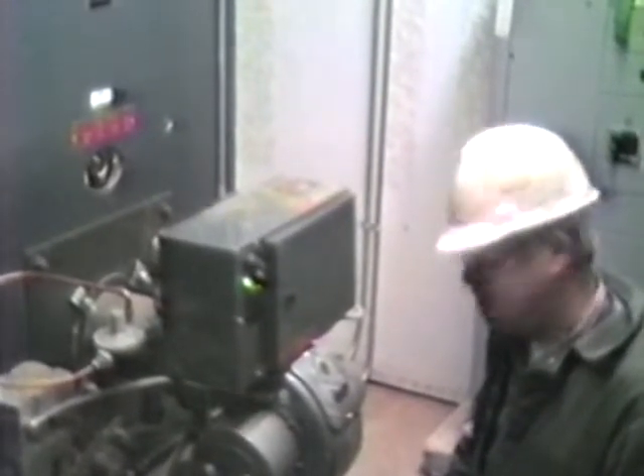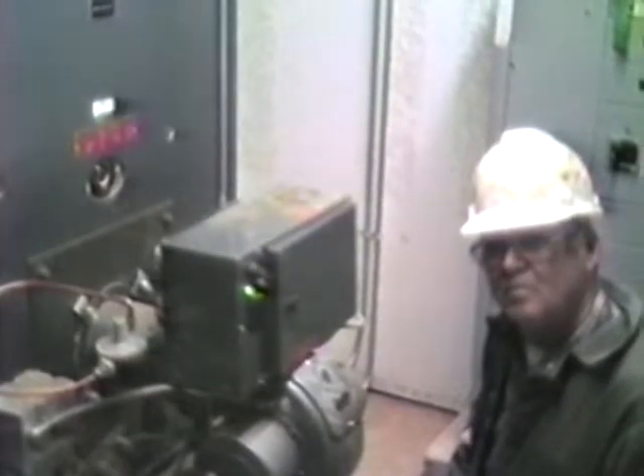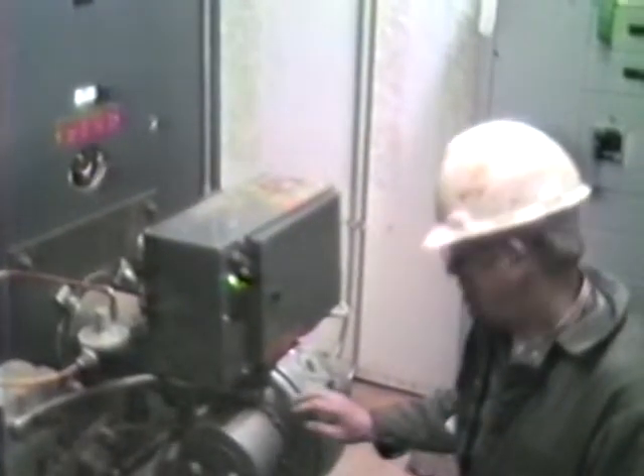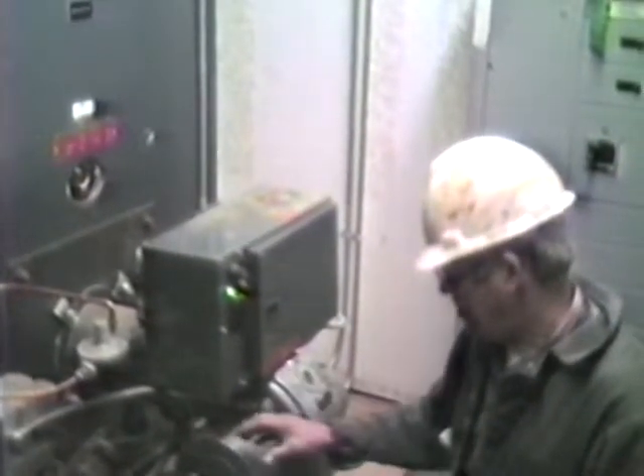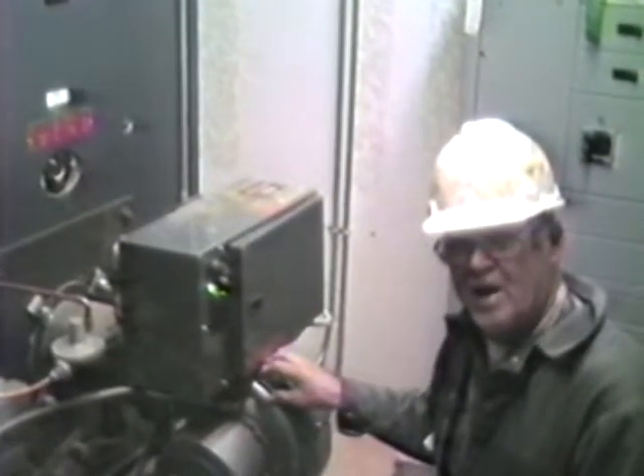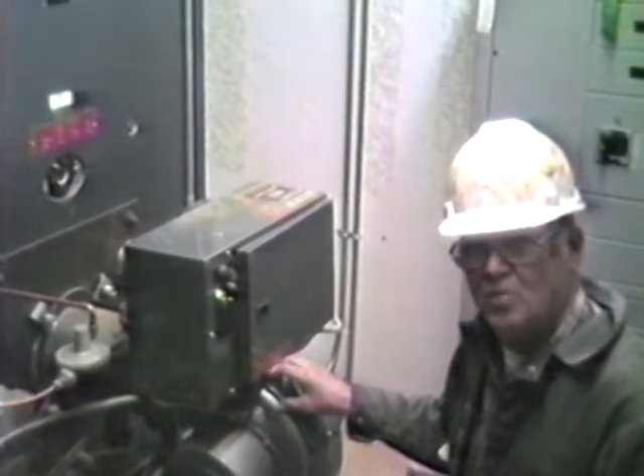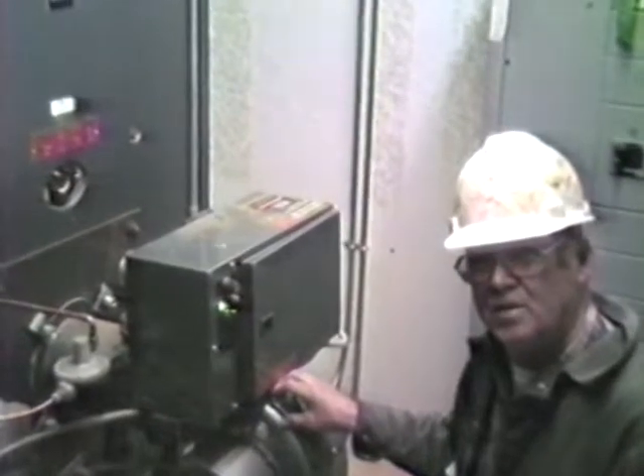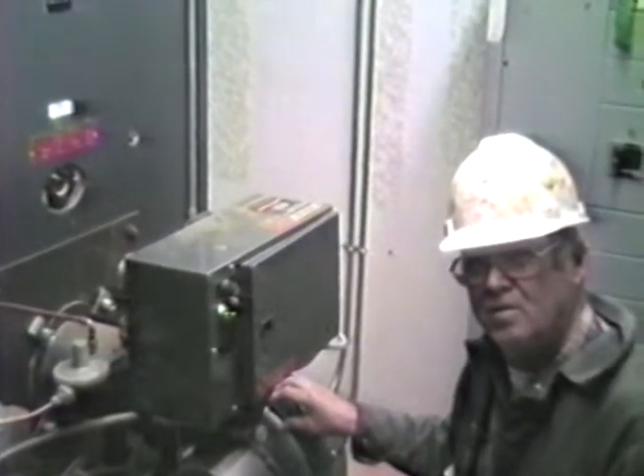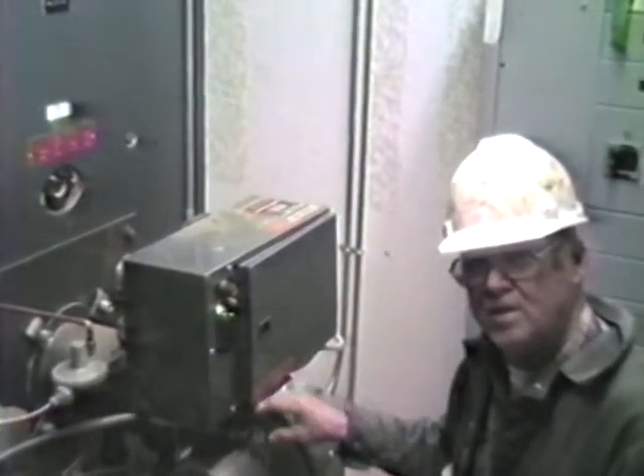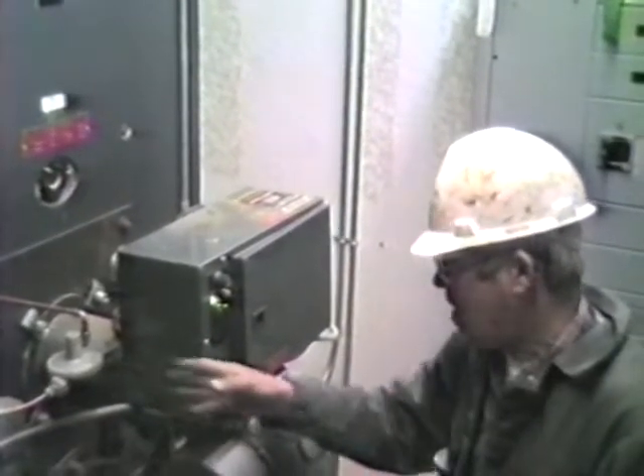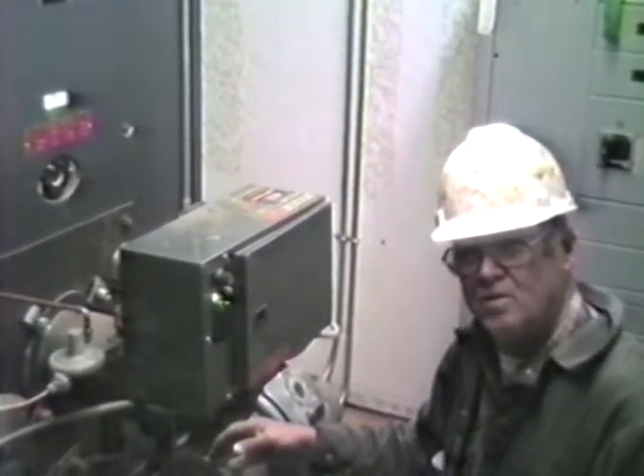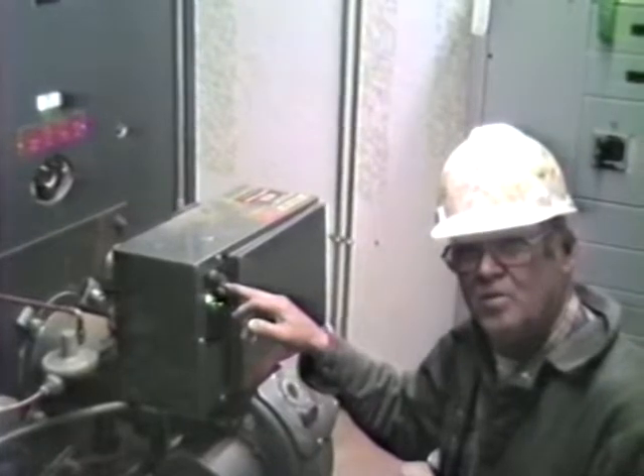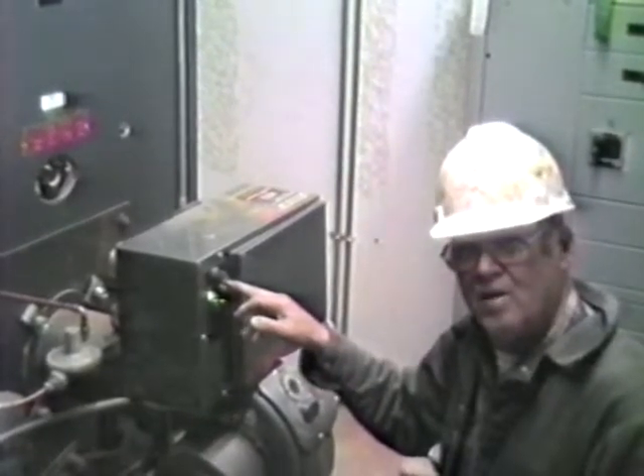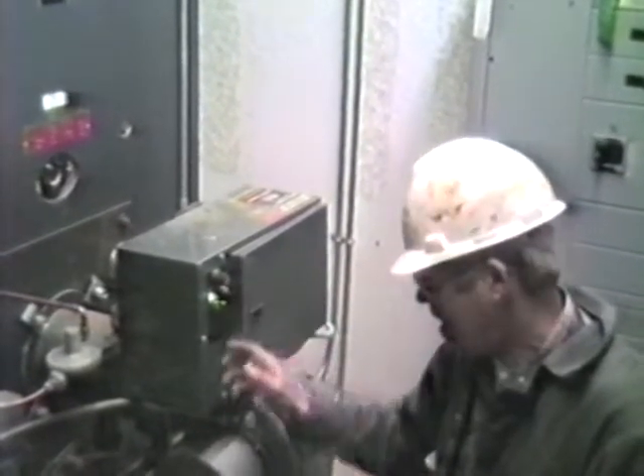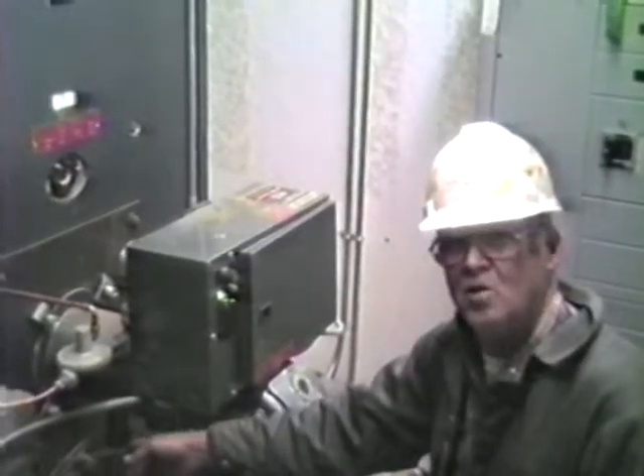As we said earlier, low fire will come on and run for how long, Roy? Now it purges itself for a minute and a half before the pilot comes on. When it starts into fire, it's low fire. When the pilot is lit, when this light comes on, it goes on to low fire. And thereafter you can watch this arm move.